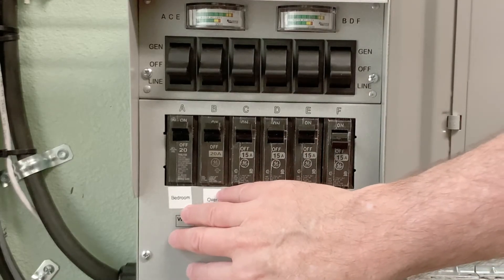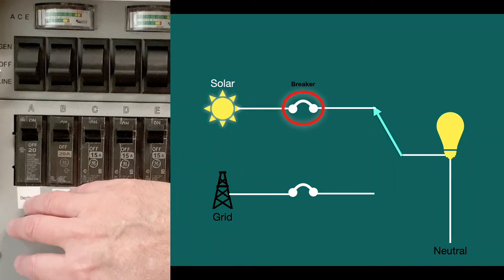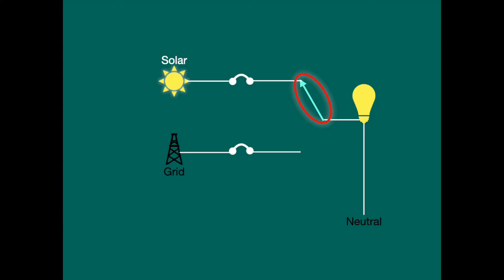Now let's take a quick look at these six circuit breakers. The circuit breakers in the transfer switch are only used when you're on solar or generator mode, and when you switch over to the grid, you're using the existing old circuit breakers that are in your breaker panel. Notice that you can only be connected to solar or the grid. They're not interconnected, which means it's impossible for this to backfeed when you're running your solar energy. You cannot backfeed accidentally to the grid.